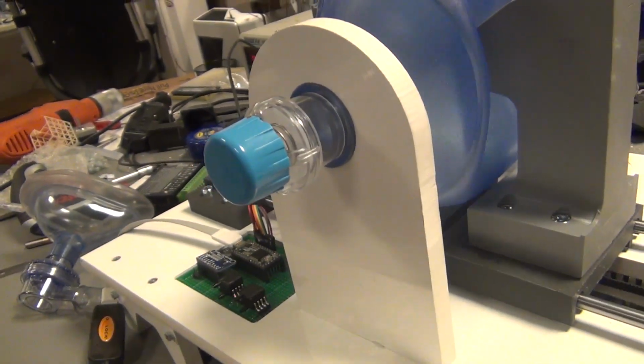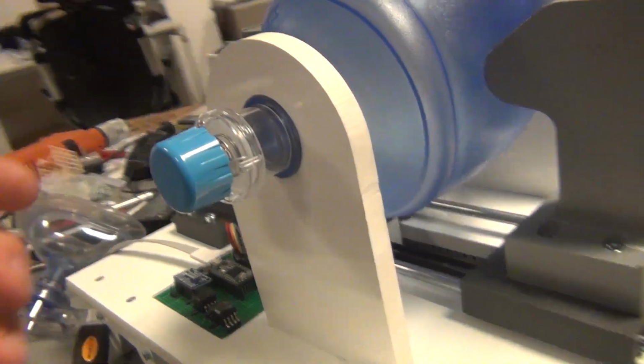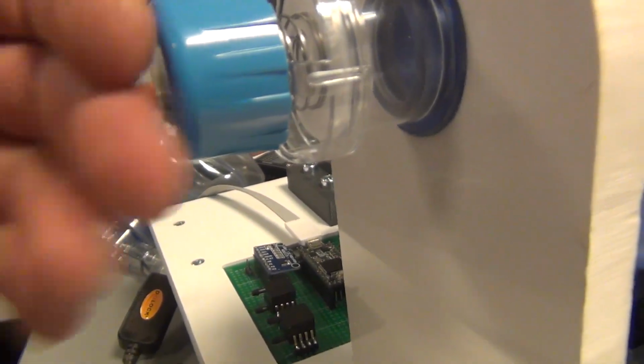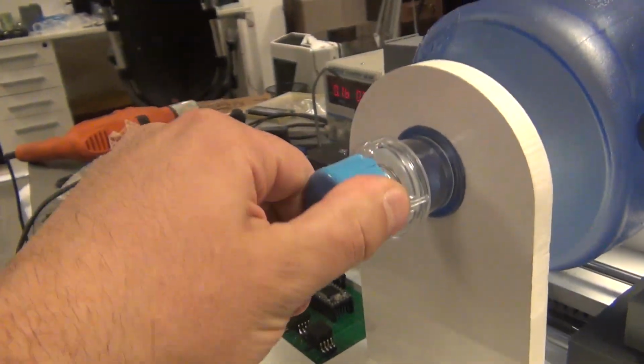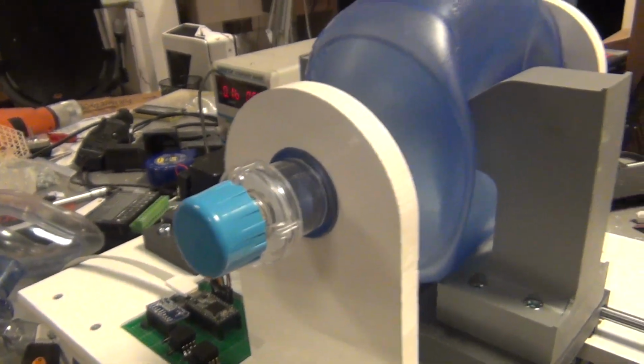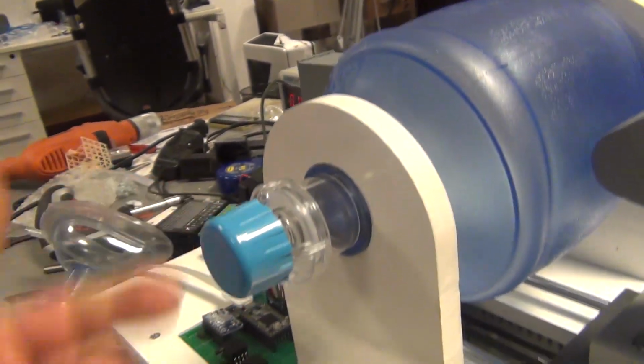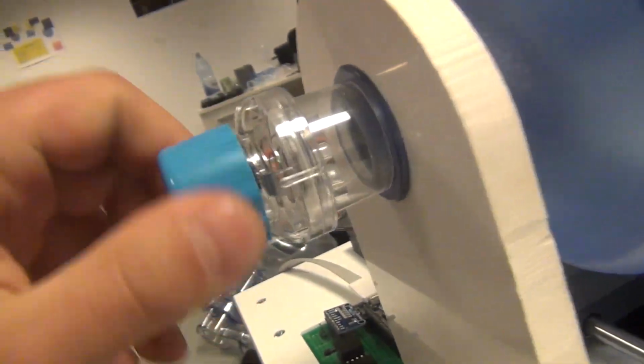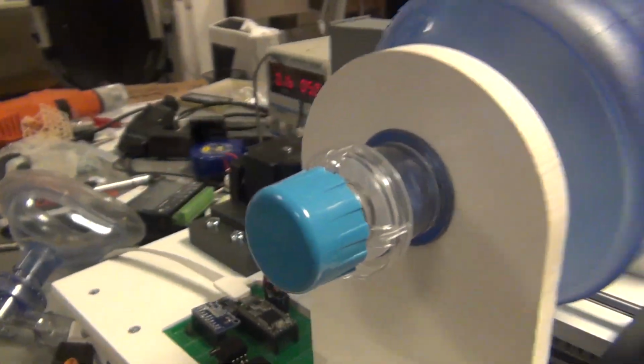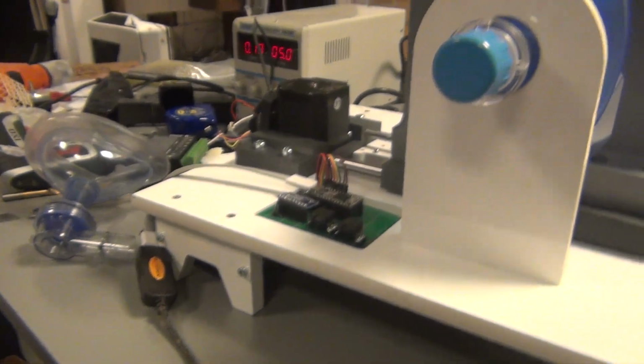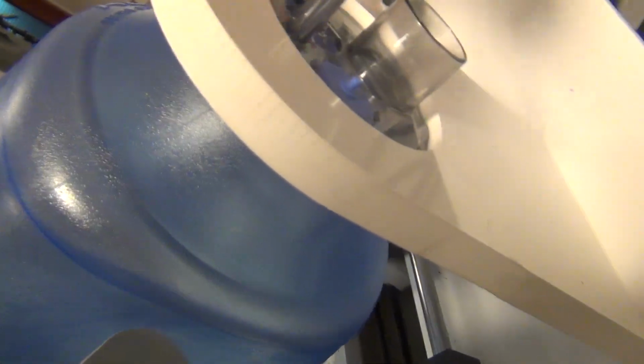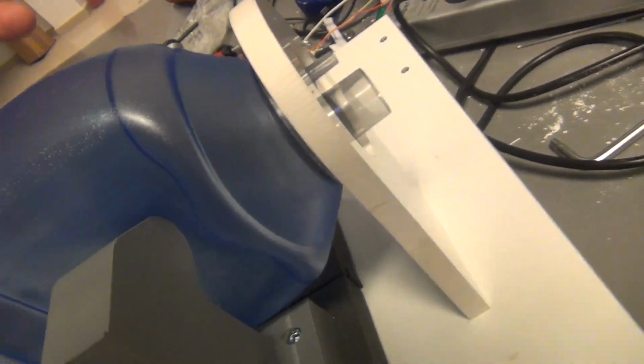But we'll also use this as a safety valve in case the airway is blocked. You don't want to push air, so we can make the spring harder in here, so it increases the resistance. But at this point, I think it's just fine to be used as a safety valve when you go over the set max value here. So we see the spring is still going a couple of millimeters. So yeah, the oxygen goes here, so you have the port for oxygen. The bag will fill in the back. I don't have it here because it's accommodating.